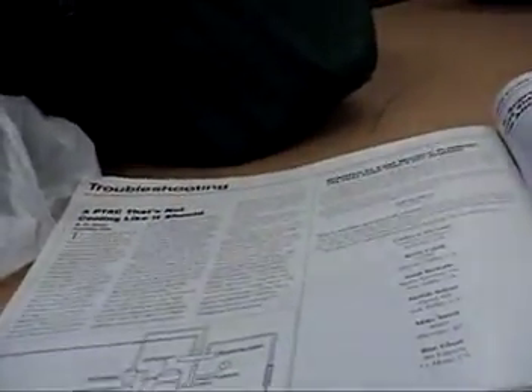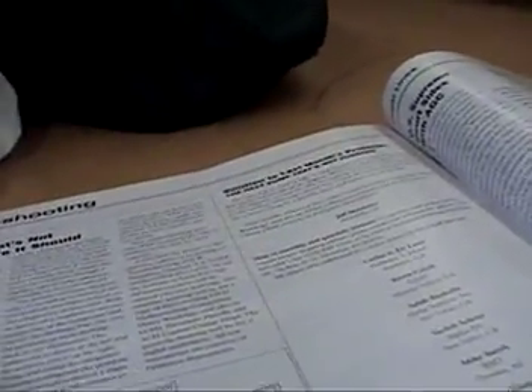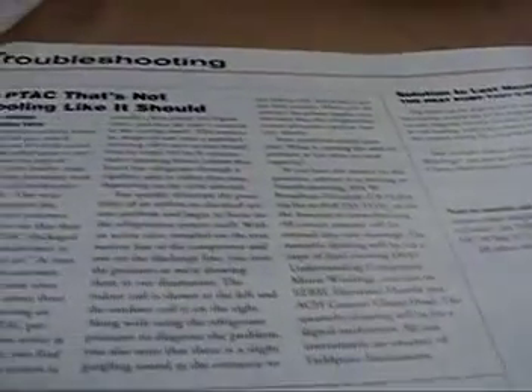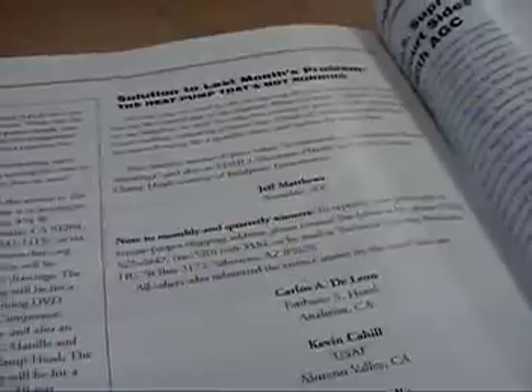Let's see, what did we say it was? Do you remember? Low voltage fuse, blown on low voltage control voltage, short to ground. Really? Short to ground fuse problem. The next step we need to take on the repair of this unit: the 24 volt blown fuse on the control side of the diagram. Blown fuse on the control side means the secondary of the transformer. And I said usually it's a short on the secondary somewhere, okay?